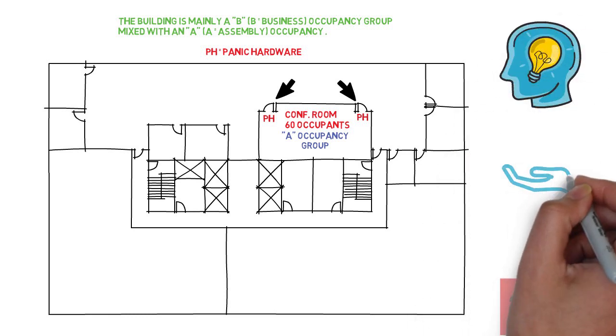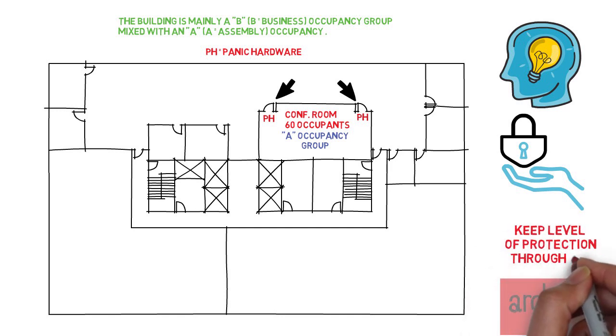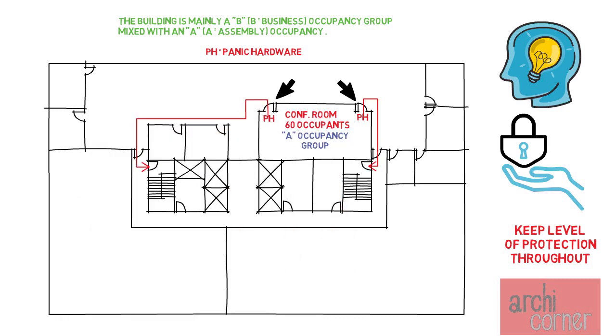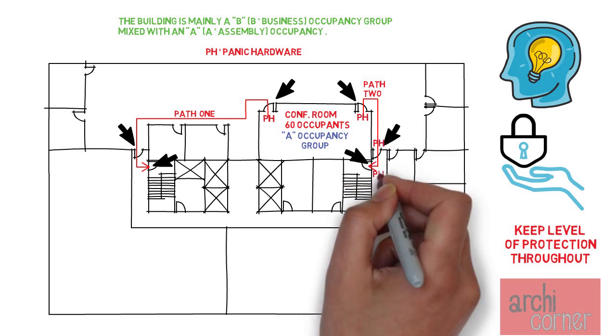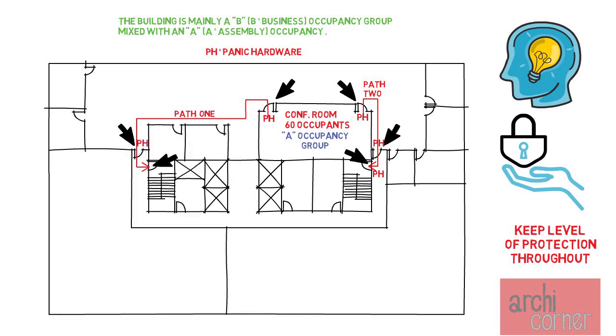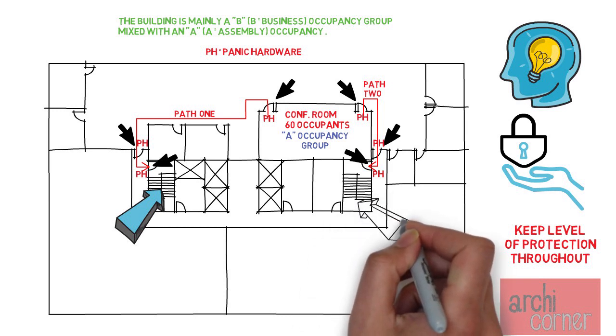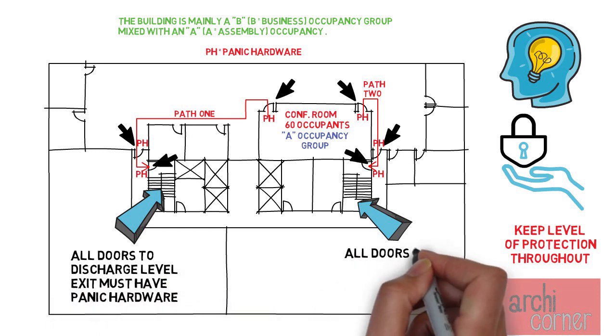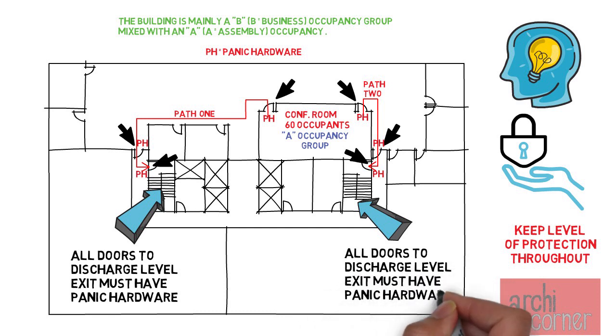One thing to keep in mind is that once you reach a certain level of protection you cannot pass into another room or area with a lower level of protection. How does this affect panic hardware? Once you're in a room that requires panic hardware, all doors on your egress path of travel all the way to your exit discharge must have panic hardware. In this example, the two egress paths each lead to a different stairway, so every door on the egress path — including the door leading to the stairway — needs panic hardware. All doors on different floors along the entire egress path also require panic hardware.